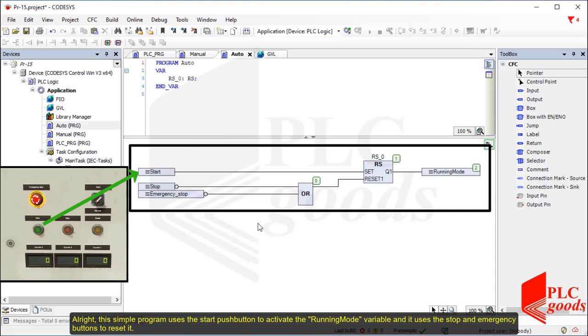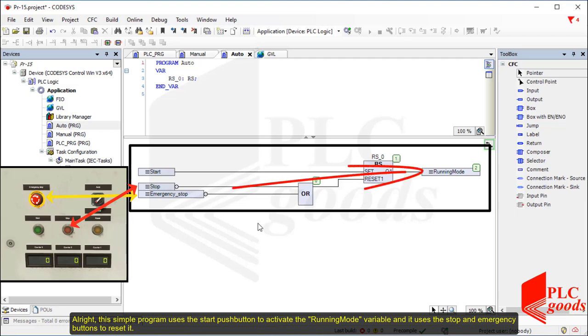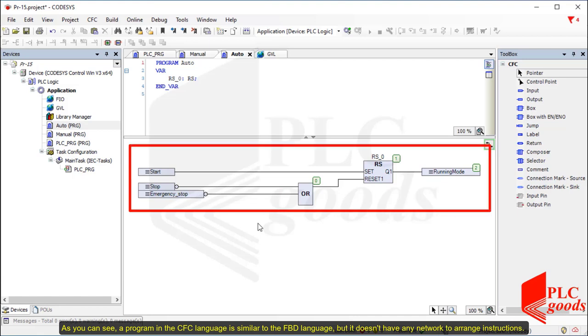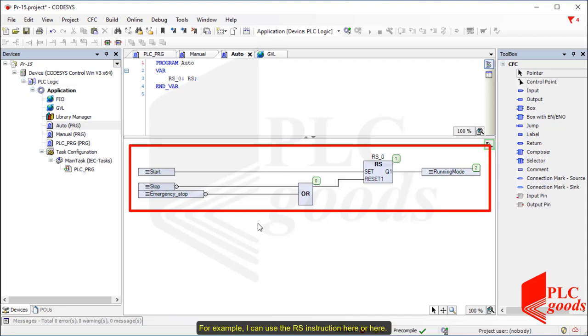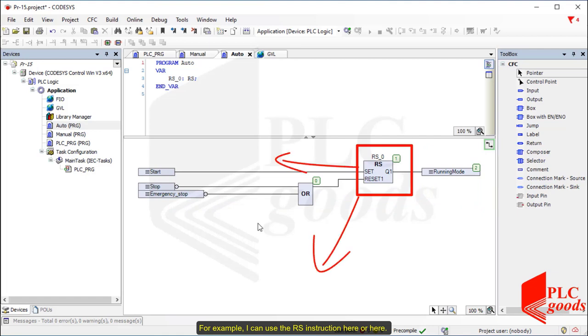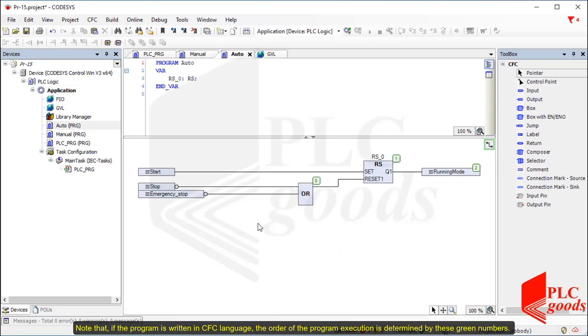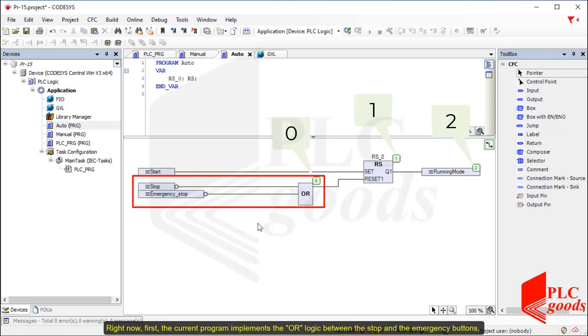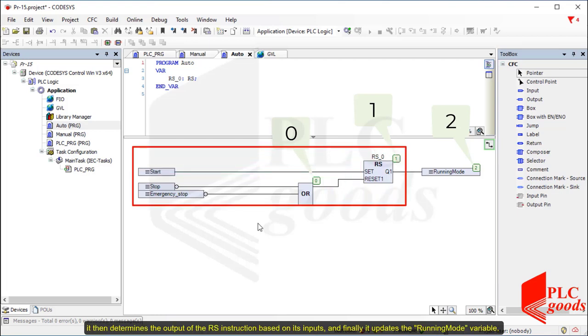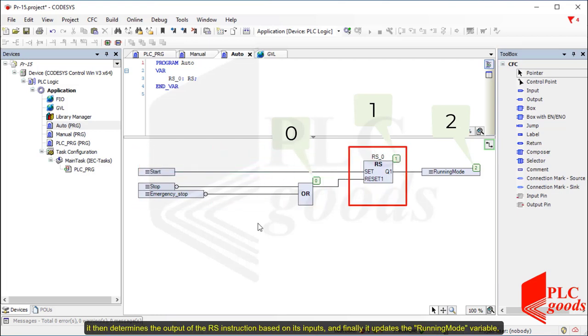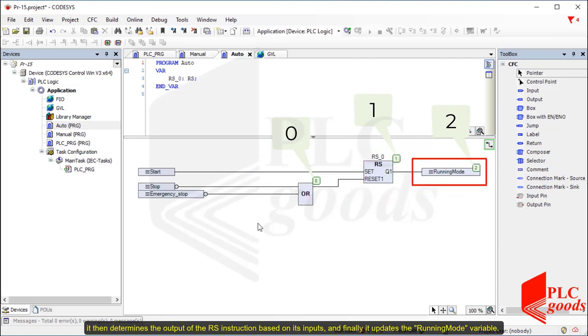This simple program uses the start push button to activate the running mode variable, and it uses the stop and emergency buttons to reset it. As you can see, a program in the CFC language is similar to the FBD language, but it does not have any network to arrange instructions. For example, I can use the RS instruction here or here. Note that if the program is written in CFC language, the order of the program execution is determined by these green numbers. First, the current program implements the OR logic between the stop and the emergency buttons. It then determines the output of the RS instruction based on its inputs, and finally it updates the running mode variable.